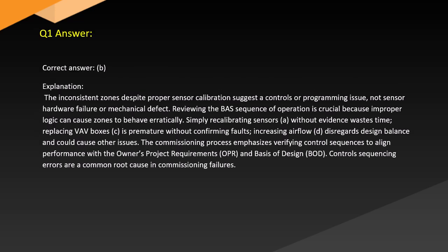Answer. Correct answer: B. Explanation. The inconsistent zones despite proper sensor calibration suggest a controls or programming issue, not sensor hardware failure or mechanical defect. Reviewing the BAS sequence of operation is crucial because improper logic can cause zones to behave erratically.